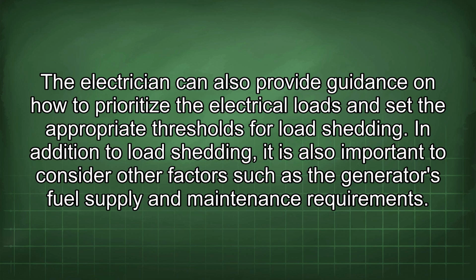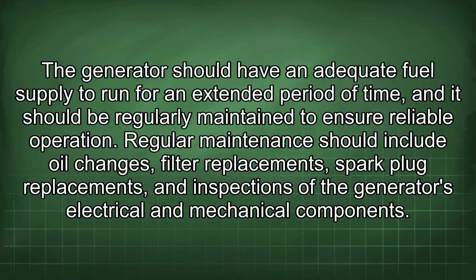shedding. In addition to load shedding, it is also important to consider other factors such as the generator's fuel supply and maintenance requirements. The generator should have an adequate fuel supply to run for an extended period of time, and it should be regularly maintained to ensure reliable operation. Regular maintenance should include oil changes, filter replacements, spark plug replacements, and inspections of the generator's electrical and mechanical components.